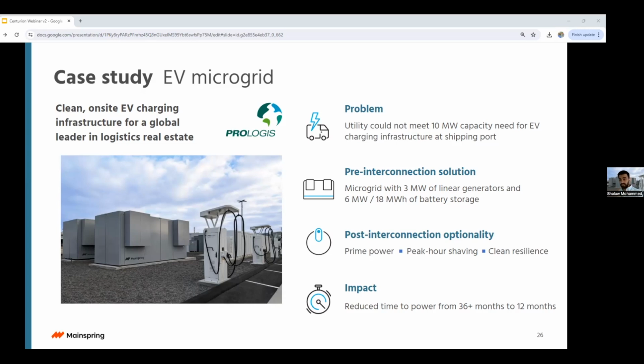When the utility gets to the site, say in 2 or 3 years, we can change our operations from Prime. We can do peak shaving depending on the rate structure, still offset utility costs by running Prime and charging batteries, or simply run in backup mode when the utility is not available.